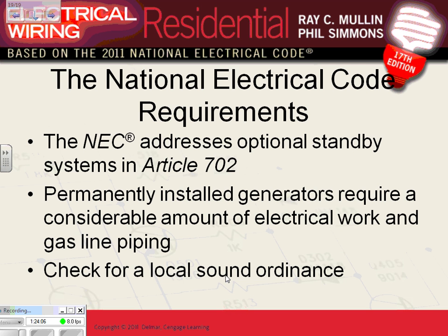So if you're installing one, Ashley, at your farm, probably don't care much. But if you're installing in the city where my neighbor is right next to me, I might have to check with the city. What do you do, by the way, if it's too loud? You have to buy an attenuating enclosure. They have it, but it makes your equipment what? Jack the price of the equipment higher. So it's not like you can't have one. If there's a sound or noise ordinance in your city, then you have to buy an attenuating enclosure that mitigates the noise, so your neighbors are not annoyed in the middle of the night when your generator is up and running.